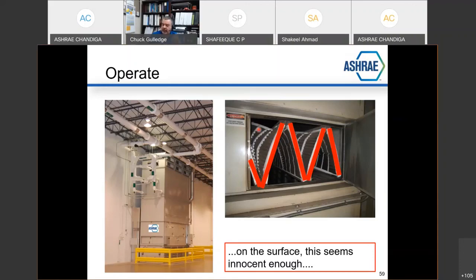Now I hope you can pick up on this. This side of the filter looks dirty, and this side of the filter looks dirty. We discovered that they were turning the filters over when the upstream side got dirty to put the downstream side now on the upstream side to load that side of the filter. These filters had collapsed. I wish I could have gotten a picture inside, but I couldn't. One of these filters got sucked up into the propeller fans that sat in this area right here, destroyed one of the propeller fans, all because somebody did not understand what proper filter maintenance was and when filters needed to be changed.